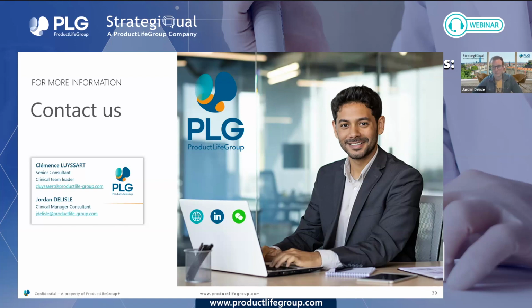And there are several examples at the end of the document that can help you. For analytical performance of a software, you may have specific analytical criteria that are different from a classic IVD. But you also have the classical ones such as analytical sensitivity, analytical specificity, etc. for your software. So yes, it's very clear in the MDCG guide.